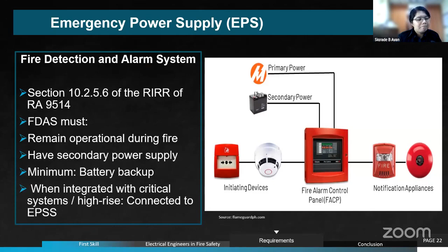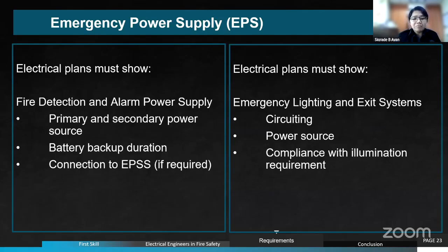So from our discussion of emergency power supply and illumination of means of egress, what should we see in our electrical plans? For the fire detection and alarm power supply, we should have the primary and secondary power supply, and we should see the battery backup duration. If EPSS is required, we need to see the connection to the EPSS in the plan. For emergency lighting and exit signs, we should see the circuiting, the power source, and compliance with the illumination requirement—every corner or part of the means of egress should be well lit.